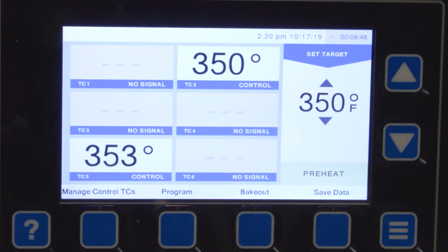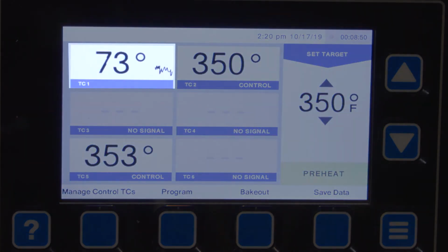This image depicts that noise is detected within the TC reading. The most likely cause is that a welded TC lead has broken loose and should be reattached or replaced. The other possibilities are that a TC probe is damaged, or a TC lead is routed with the direction of induction heating cable and the lead should be separated to address the issue.